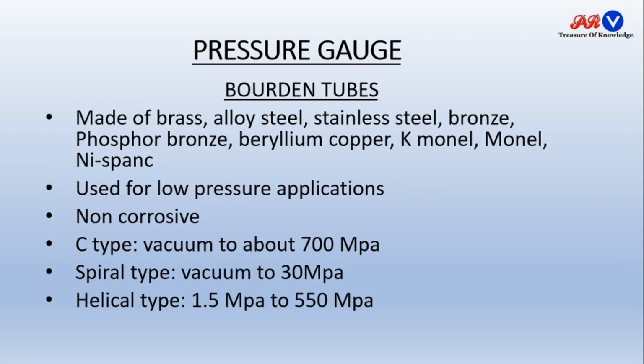Bourdon tubes, this is some specification. These are made up of brass, alloy steel, stainless steel, bronze, phosphor bronze, beryllium copper, K-Monel, Ni-Span-C metals. Used for low pressure applications. Bourdon tubes are only used for low pressure applications. These are non-corrosive, as they are made up of some alloys, so they are non-corrosive.